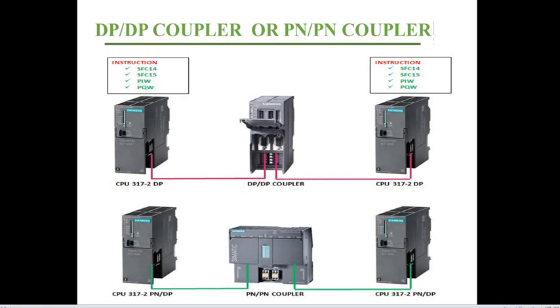For the second communication type, we use a coupler — this is the most common and most used in practice because the coupler separates the two networks. For Profibus, if the two PLCs have the same Profibus address, there is no option to connect them directly, so we must use the coupler to solve this problem.